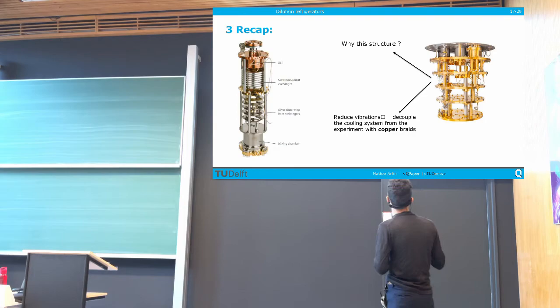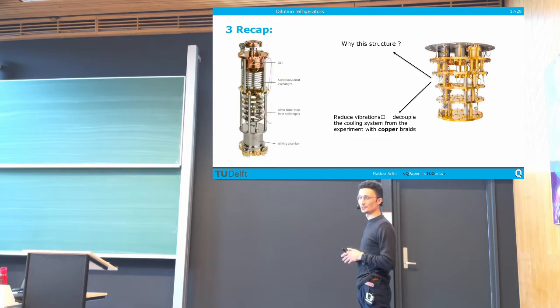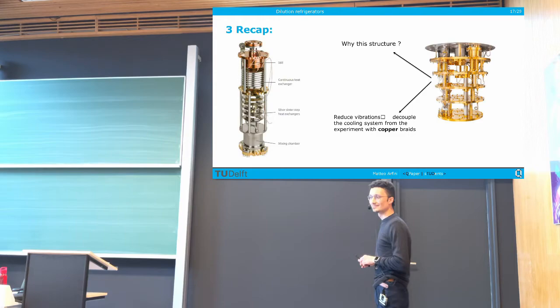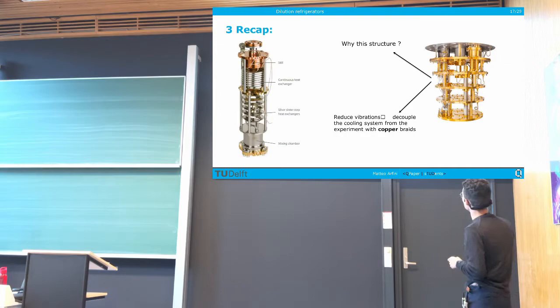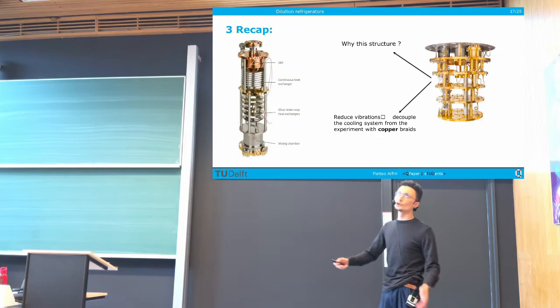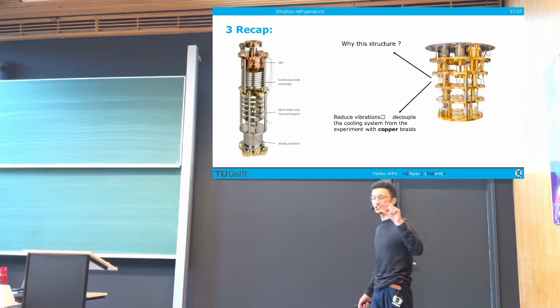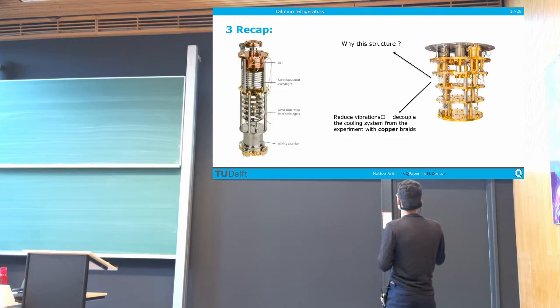Here is an example of a dilution refrigerator for quantum computing. Why does it have this specific step-wise structure from top to bottom? The main reason is to reduce vibrations, because these systems are connected to vacuum pump systems. In modern cryogenics it is usually done in a dry way, meaning special pumping systems are used to reach low temperature. By means of a series of copper braids, we can decouple the experiment from the vibrations occurring in the upper stages.